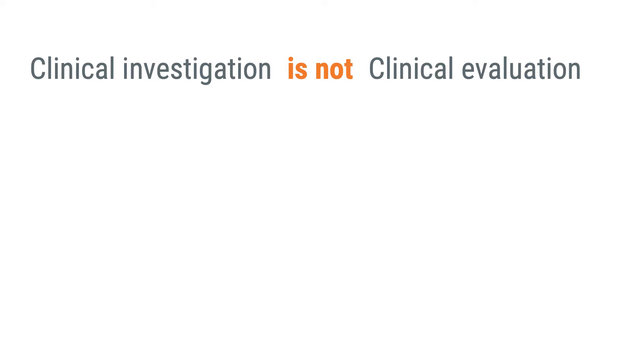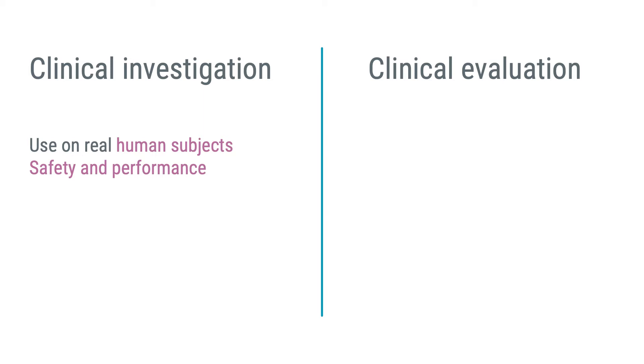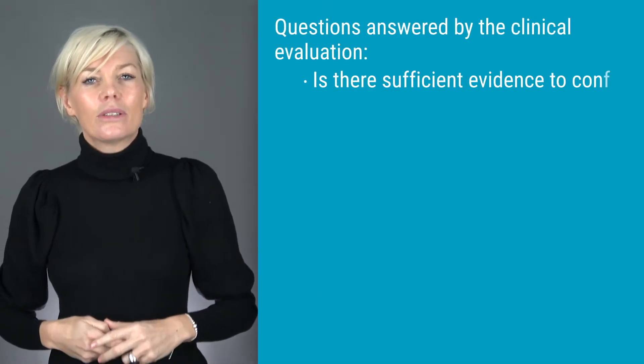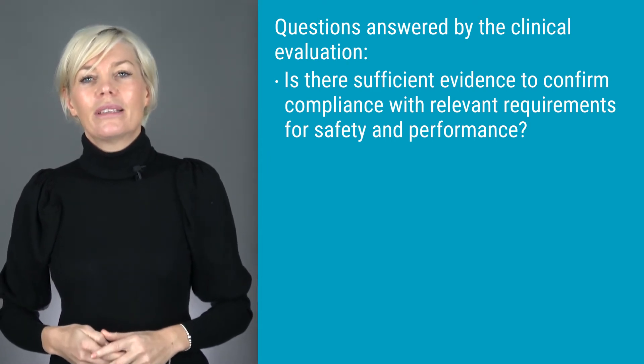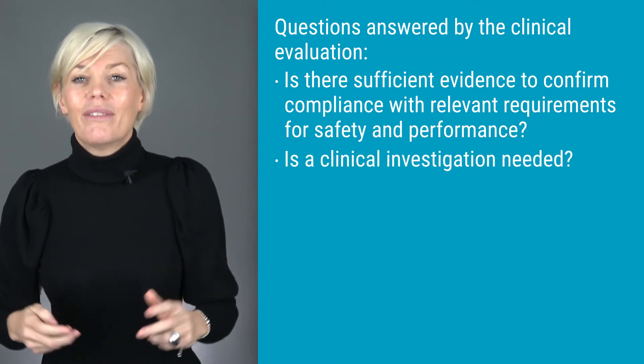It is easy to misuse or use these terms interchangeably, but it's important to know the difference. A clinical investigation is when you are using a medical device on real patients to demonstrate the safety and performance of that medical device. Whereas a clinical evaluation is a theoretical and scientific assessment of existing data from many different clinical investigations and other sources of clinical data. The clinical evaluation answers two important questions: is there sufficient clinical evidence to confirm compliance with relevant safety and performance requirements, and is a clinical investigation needed?